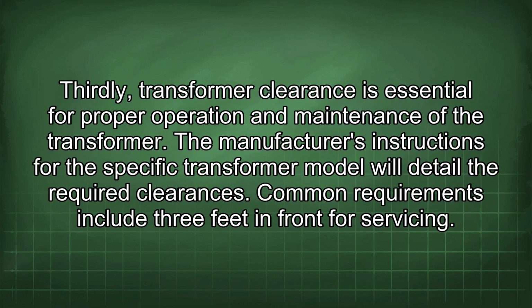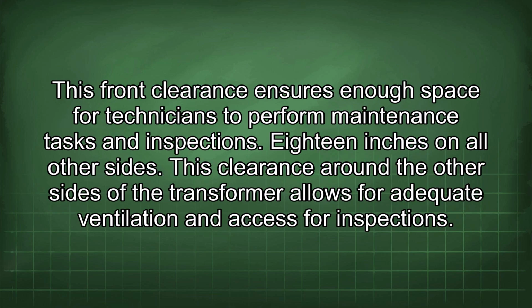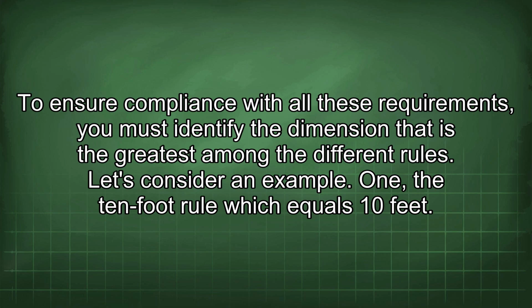Thirdly, transformer clearance is essential for proper operation and maintenance of the transformer. The manufacturer's instructions for the specific transformer model will detail the required clearances. Common requirements include 3 feet in front for servicing. This front clearance ensures enough space for technicians to perform maintenance tasks and inspections. 18 inches on all other sides. This clearance around the other sides of the transformer allows for adequate ventilation and access for inspections. To ensure compliance with all these requirements, you must identify the dimension that is the greatest among the different rules.